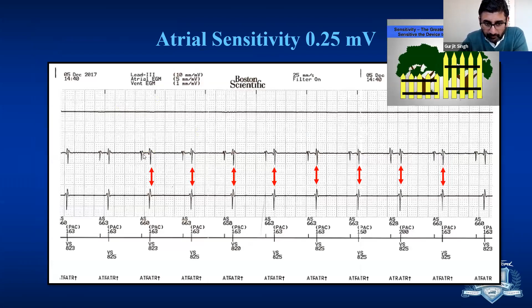So sometimes this is an example to show you that the device clinic may come back, saying the patient's lead is failing or the threshold is high. And the other way to do it is, if you have any trouble, obviously this is not a dependent patient, you can always test in AOO mode. AOO mode is basically you are turning everything asynchronous.